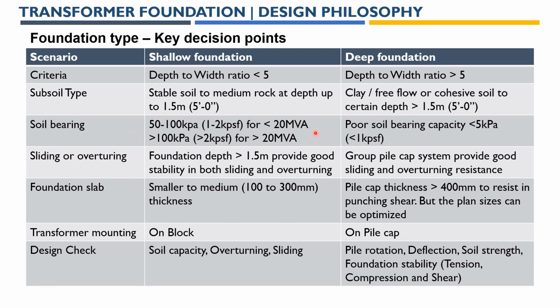This case is mostly applicable if the transformer base slab can distribute all the transformer loads to the soil over the same area, then we can go for shallow foundations. If the soil bearing is very poor, unable to hold even less than 5 kPa or 1 kilopound per square feet, then we need to go for deep foundations.